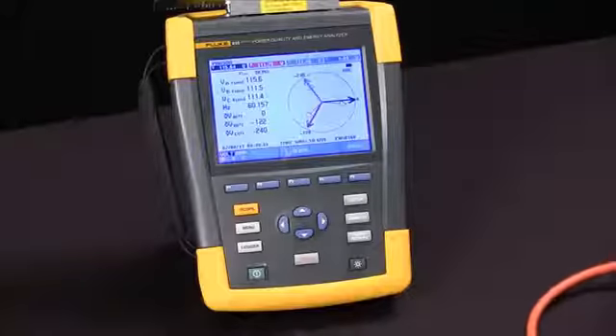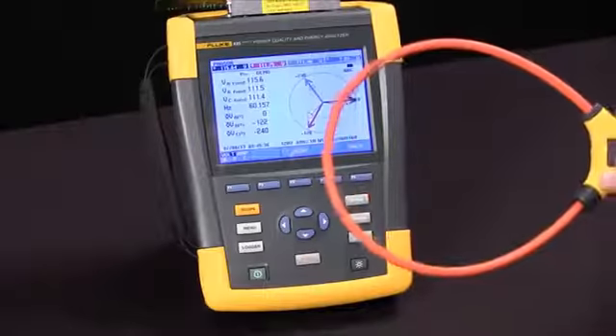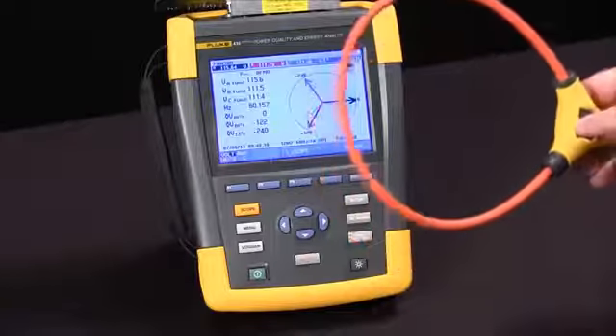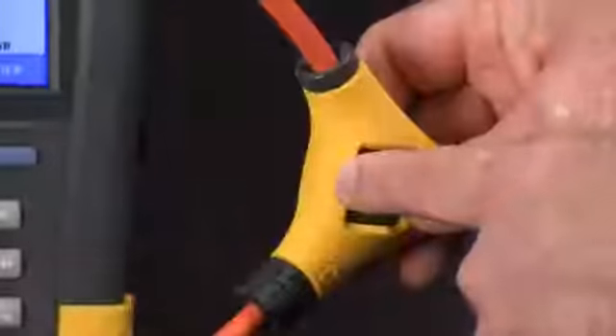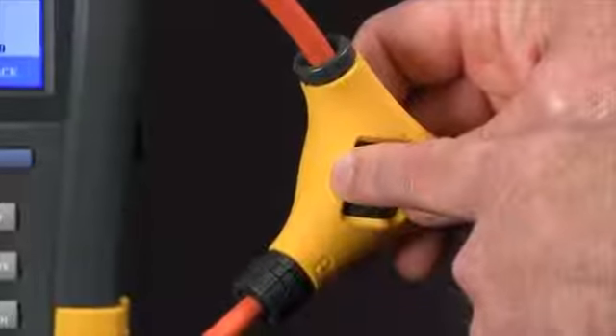The way to see when you have a difference, or if you need to make a correction for the current clamp, is to look for an arrow on the inside of the CT that should be pointed towards the load.